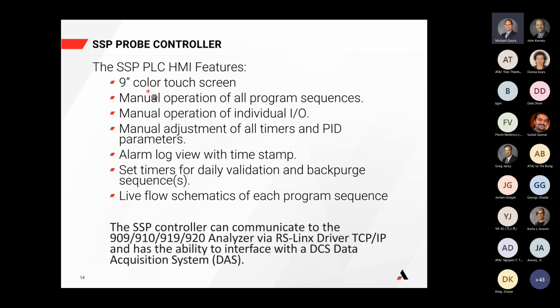So again, I'm going to try and keep us moving here. It is a good size color touchscreen, 9 inches. So it provides an easier way for users to interact both back to the analyzer as well as up to the probe assembly, and not try and do that from the actual analyzer itself. This is a dedicated screen that users will be able to operate either manual sequences that they can go through, or they can configure it to set up some automatic blowbacks or other automatic events, including auto zero, calibration, or even a validation. It does have an alarm log view. Again, I'll have a slide dedicated to that coming up in a little bit.